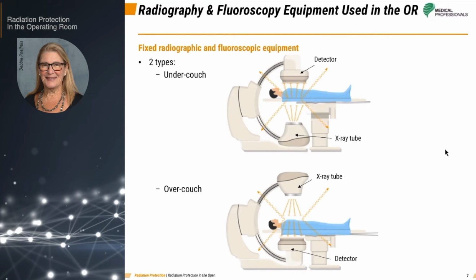These two systems differ most in terms of radiation exposure to the operating room staff, namely which part of the body receives the greatest exposure as a result of the positioning of the X-ray tube. Over-couch systems may expose OR staff to higher radiation doses than under-couch configurations.